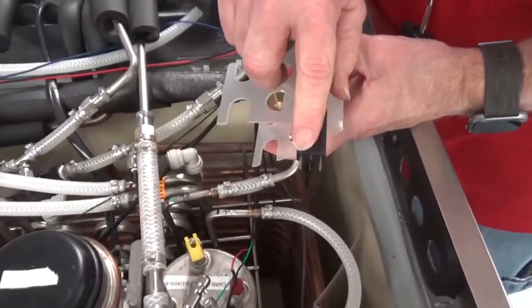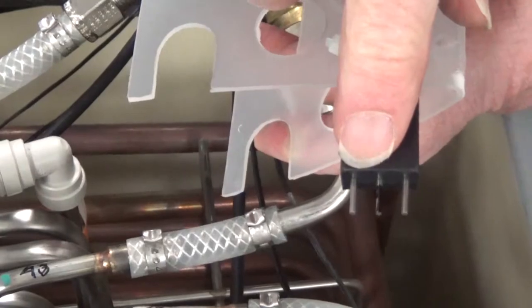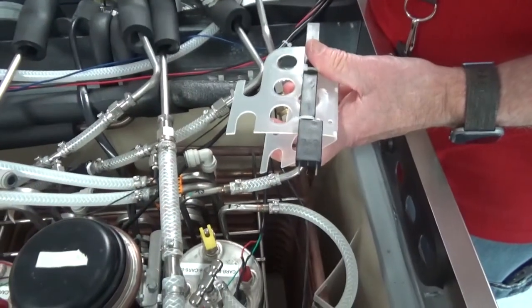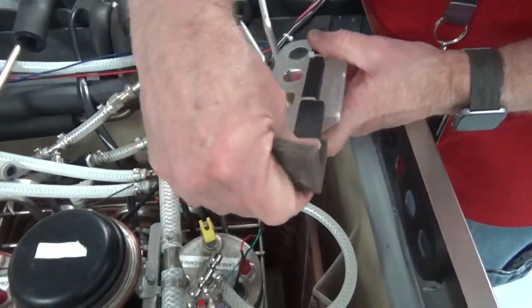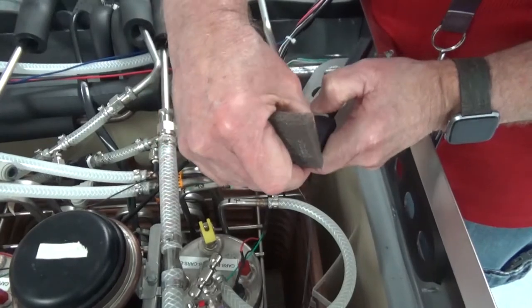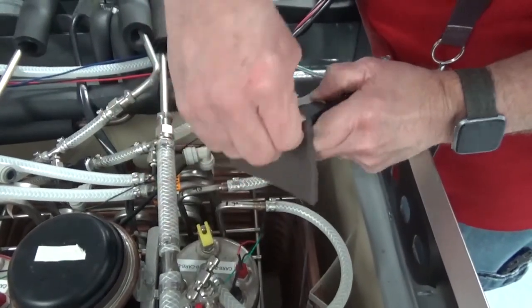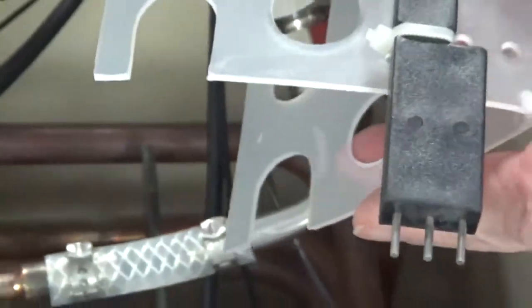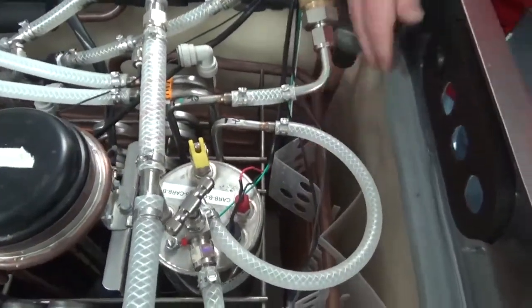Inspect the three pins on the bottom for corrosion. Clean any corrosion off the probe with emery cloth, scotch-brite, steel wool, or some other abrasive pad. Reinstall the ice bank probe over the evaporator coils.